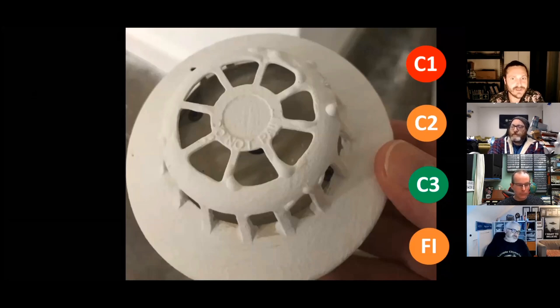And so when you go to the manufacturers, when we've looked into this before, Eddie actually sent me an article from Pegasus, and it's from a manufacturer, and it says that they haven't tested FP cables under fire conditions when they're painted. So therefore they cannot say if they will function under 5839 part one, if they're painted.